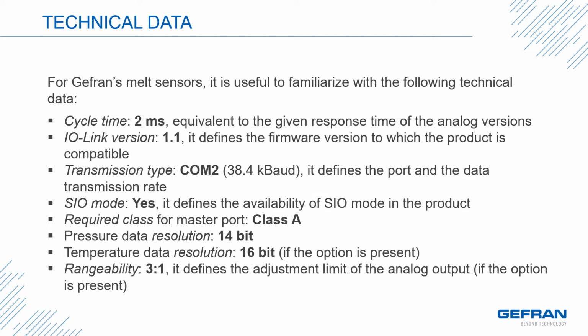Our transmission type is considered COM2, which is 38.4 kilobaud. Do we support the standard I/O mode? Yes. We are a Class A port in support of a master in a system. Pressure data resolution is a 14-bit resolution. The temperature is 16-bit. And we have a rangeability of 3 to 1 with the optional analog output.